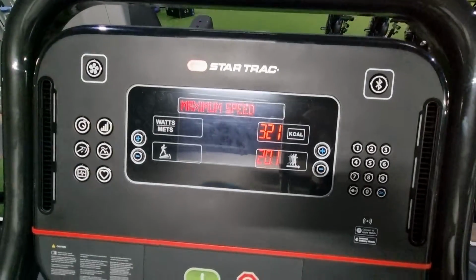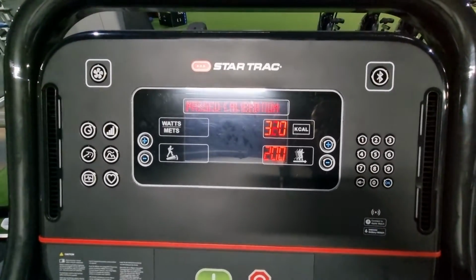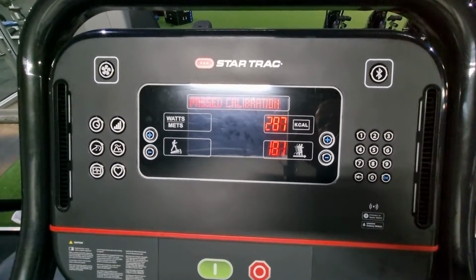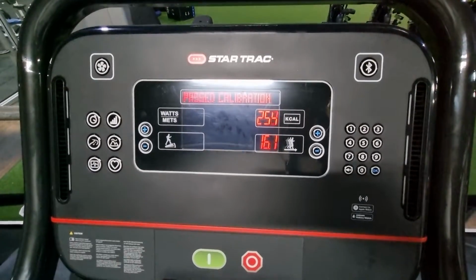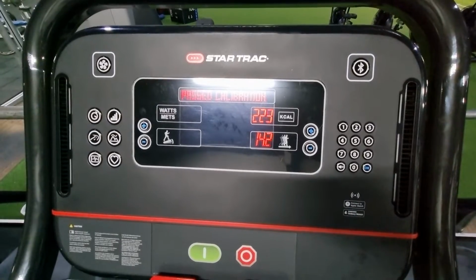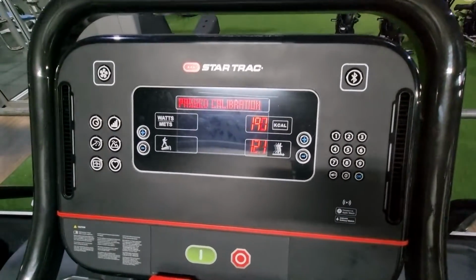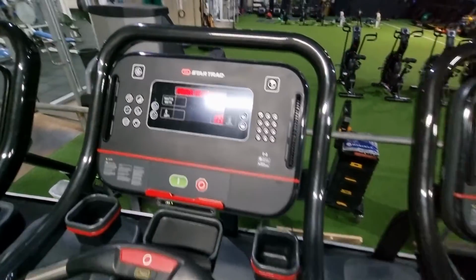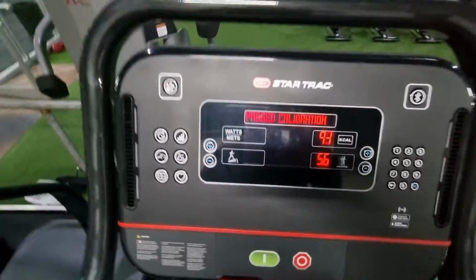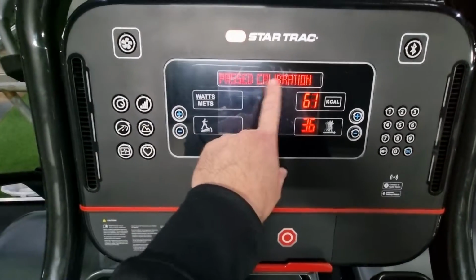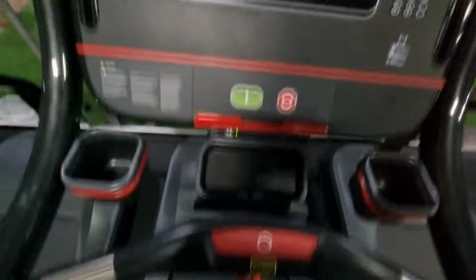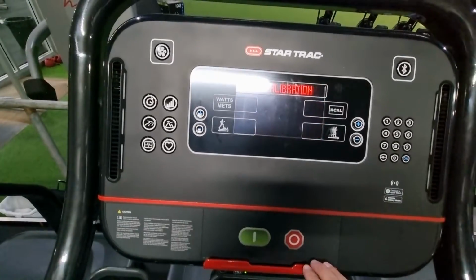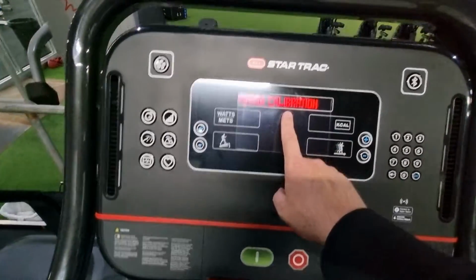So this here, it'll go to the max speed. This max speed is 20 k's. So there we go, it's finding 20. It's found that, and it's going to go back down. And just finally stop. So that says it's passed. Let me hop on here. That says that it's passed the calibration, so that's fine. That's all well and good. Just wait for the mat to fully stop there. That's stopped. And then it goes back to the motor calibration here.